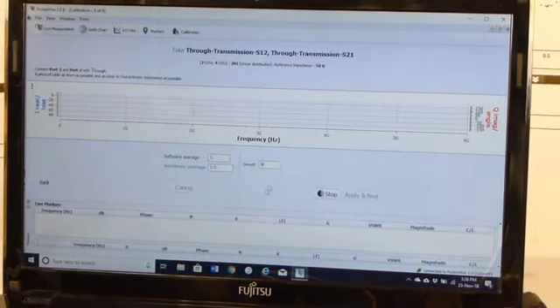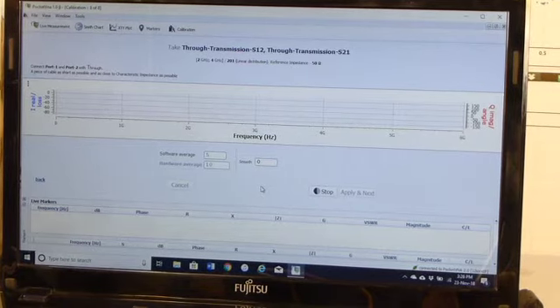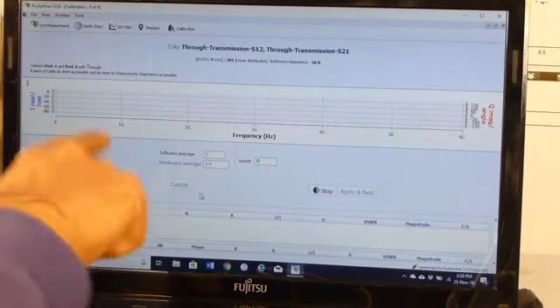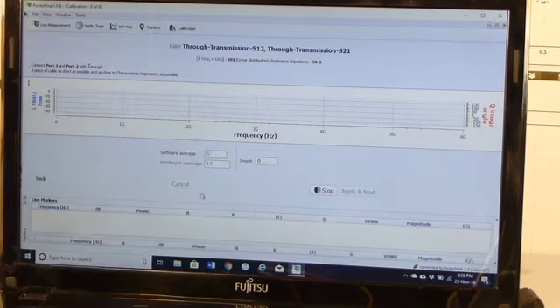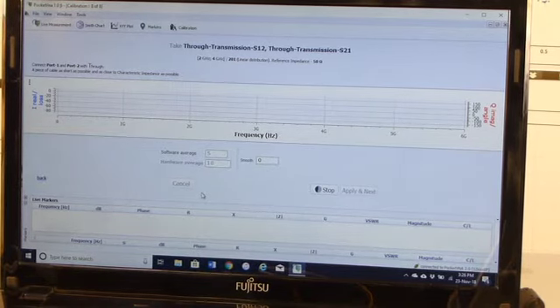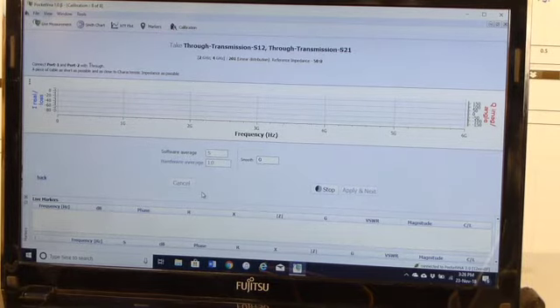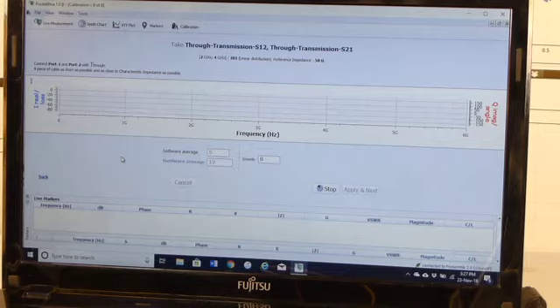Now this process of calibration can be made fast if we select the software average as 1 instead of 5 for fast operation, but then it could miss some readings. It is preferred to take the calibration file, or load the calibration file, every time we operate the VNA. For student level, we can save the file on the desktop and load it every time we operate the VNA to save time.